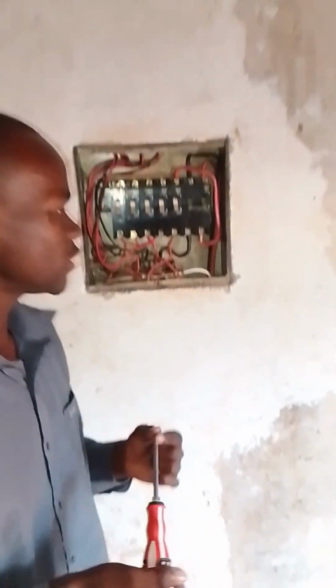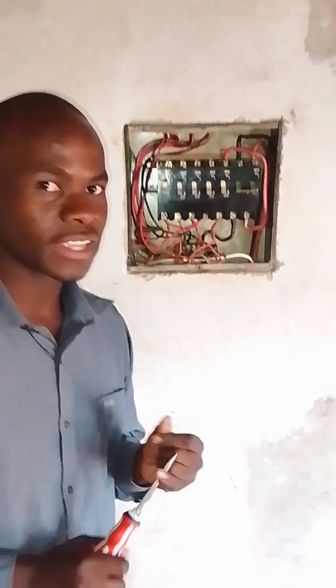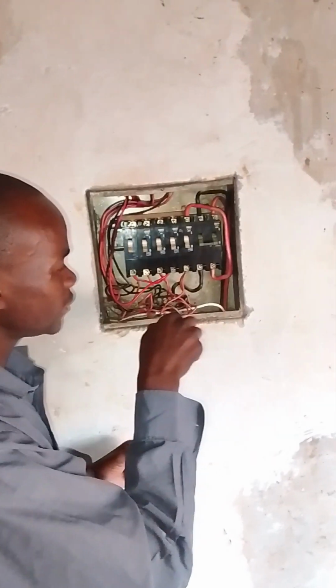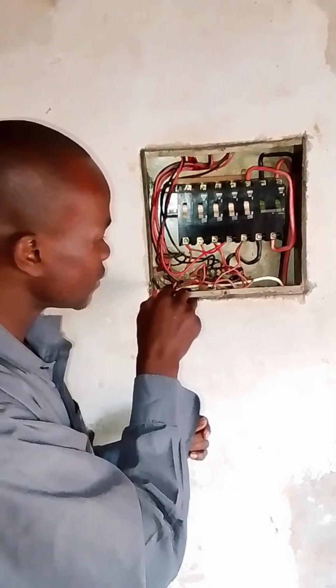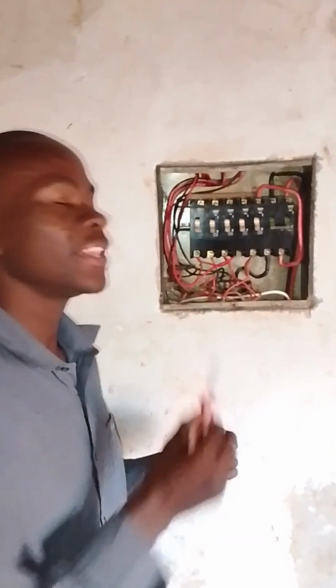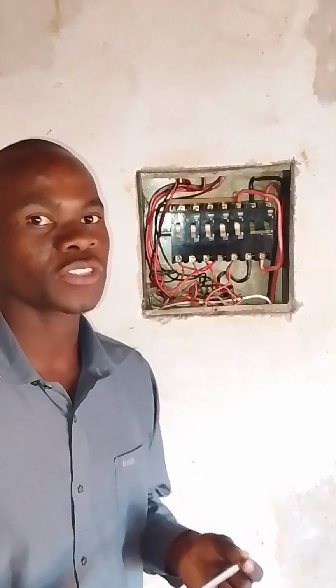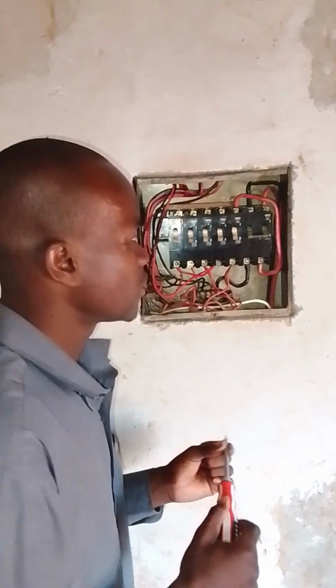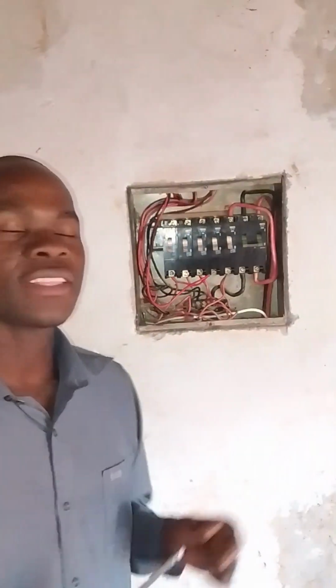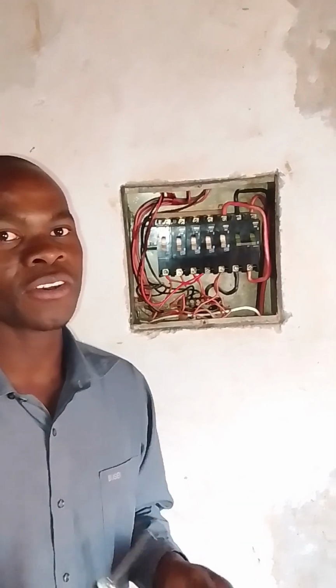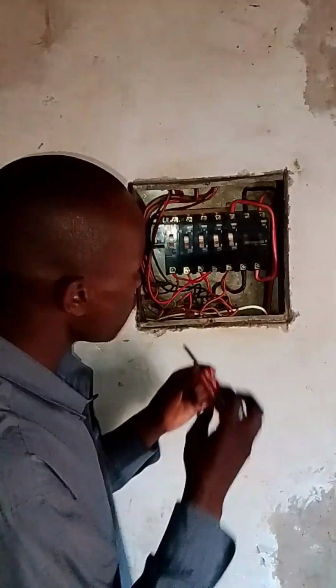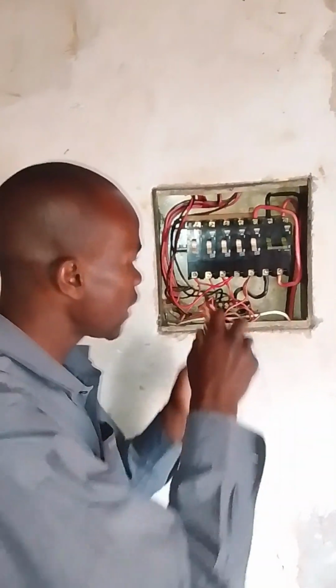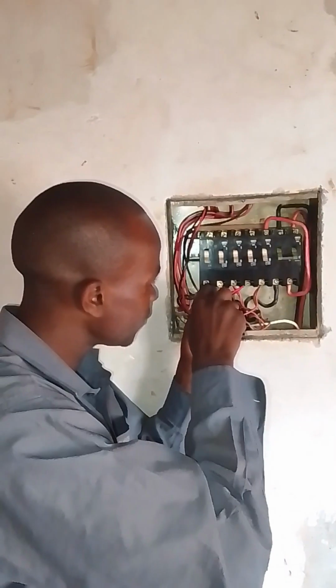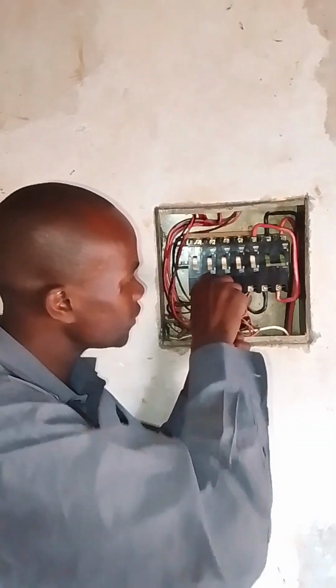After this, we have to understand that, as I said, there are 3 wires coming from the meter box, and the earth right here is placed at the bar right here. This is how it's wired, and all the earth will be wired right here, and this is done to prevent electric shocks. Like this, after you've done this, you make sure that all the cables, all the wires that you have made, are firm by screwing tightly and making sure that they're all in place.